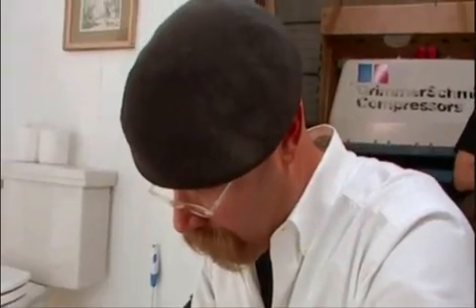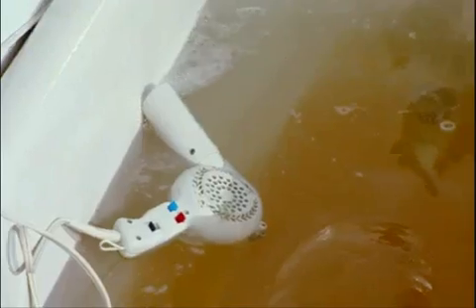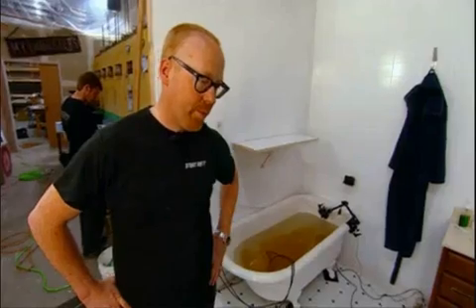Uh-oh, something's not right. Oh, look at the water flowing. It's pumping! What is our amperage? What's our amperage? 0.95 AC. What kind of ground fault interruption is this? It's pumping water! I would say that's bad! Well, the relay didn't trip and the ammeter didn't show enough amperage to kill somebody.